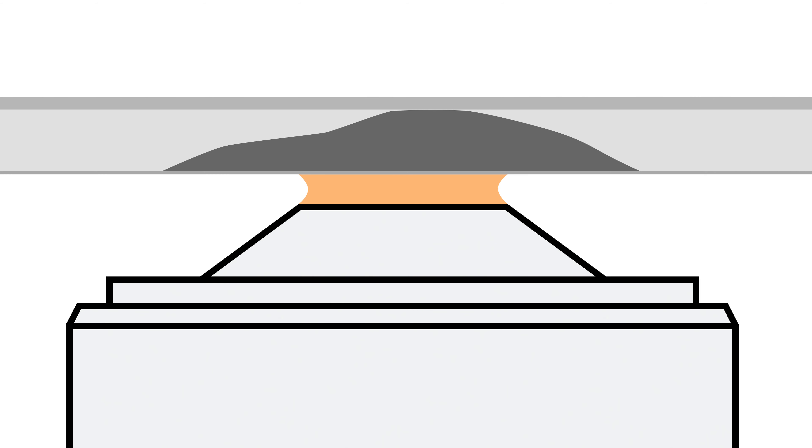To appropriately choose an immersion objective for your experiments, it is important to consider what type of medium your specimen will be mounted in. To achieve the calculated resolution of an objective, the refractive index of the immersion fluid required by the lens ideally must match the refractive index of the specimen.